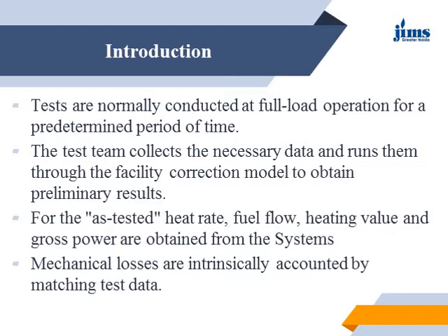So we test the plant under that condition, and the test team collects the necessary data and runs them through the facility correction model to obtain preliminary results. For the test, heat rate, fuel flow, heating value and gross power are obtained from the system. Mechanical losses are intrinsically accounted for by matching test data.